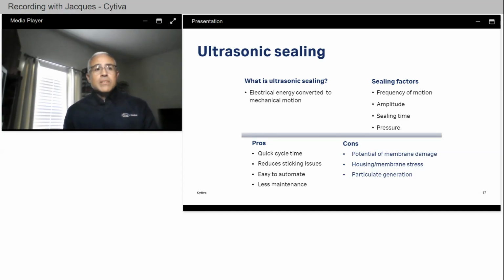Ultrasonic welders are typically available in 20 and 40 kilohertz frequencies. Next is the amplitude, which refers to the length of travel or motion of the tool during the cycle. The distance of travel per cycle is adjustable, and the degree of adjustment depends on the combination of booster horn and input power supply used. As a guideline for devices that are under 1.5 inches in diameter, we suggest a 40 kilohertz power supply. For larger diameters, we recommend a 20 kilohertz power supply. Then there is the length of the sealing time, and the pressure the tool is applying to the seal area.